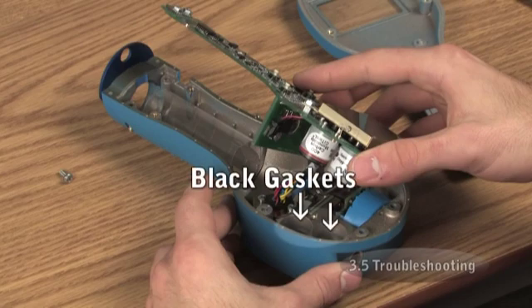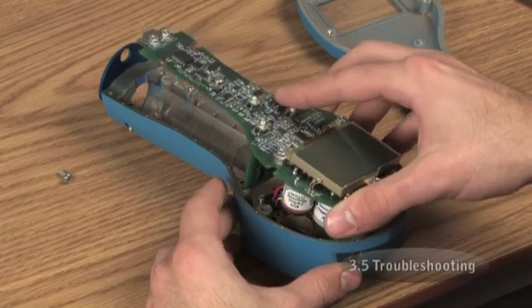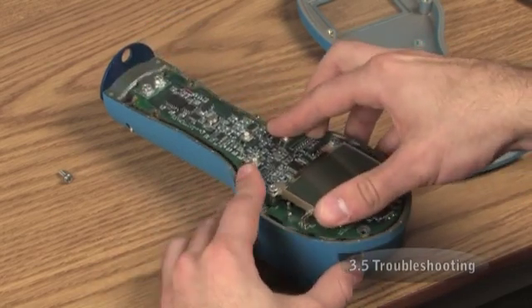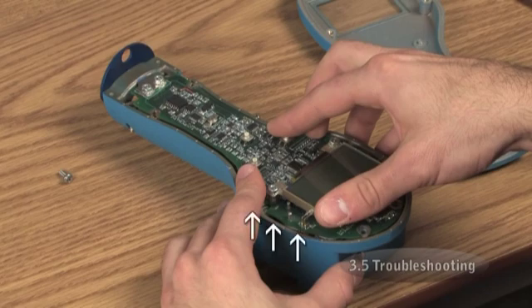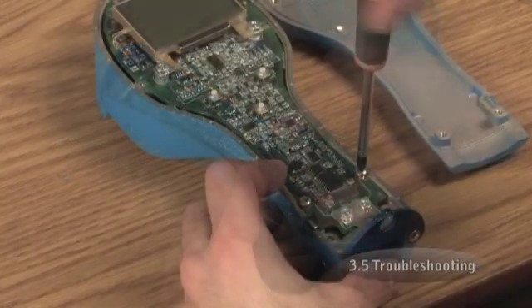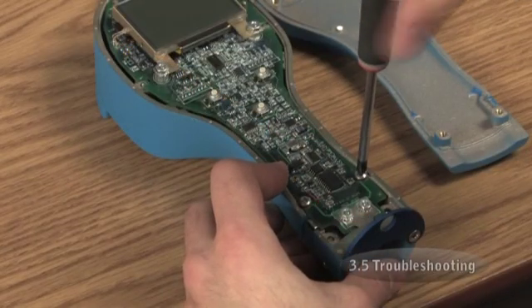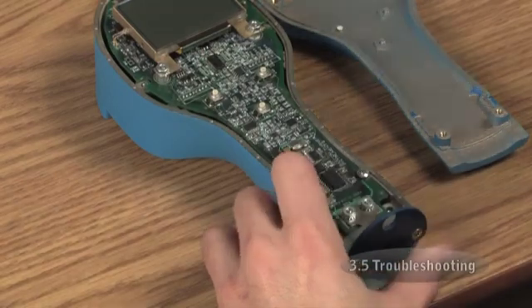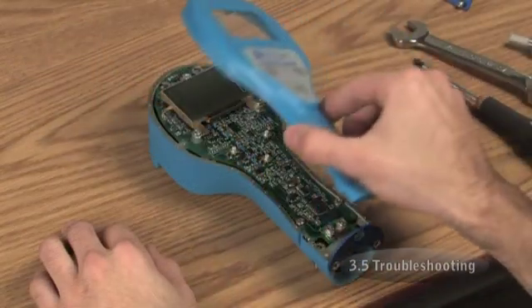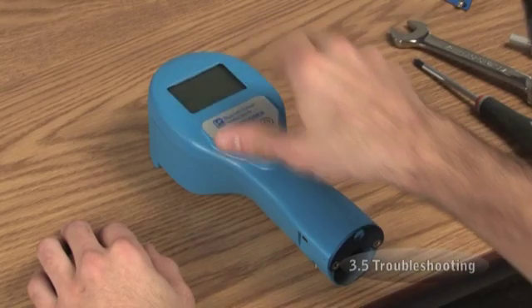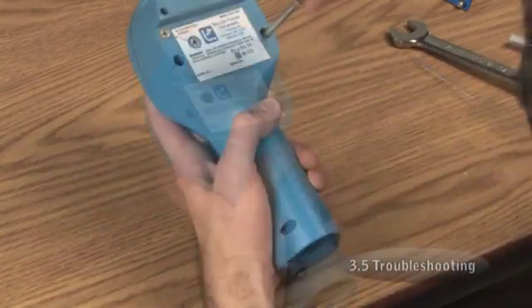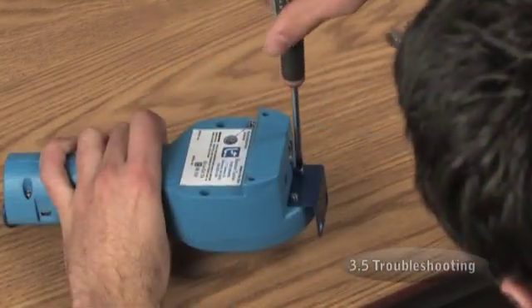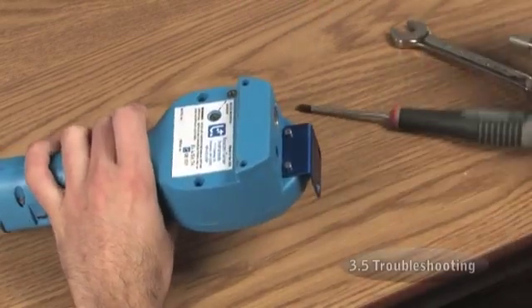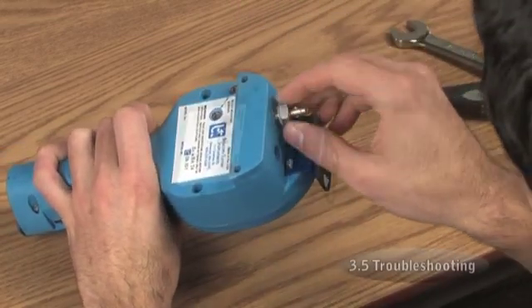Verify that the black gaskets are still in place in the sensor block and carefully replace the circuit board. With the circuit board in place, check that no methane sensor wires will be caught between the board and case. Replace the 2 circuit board retaining screws. Replace the Explorer cover and case screws. Replace the inlet filter and batteries.